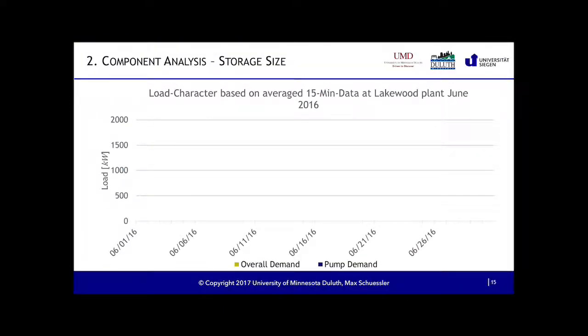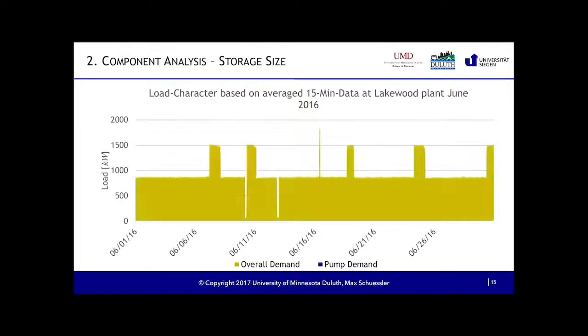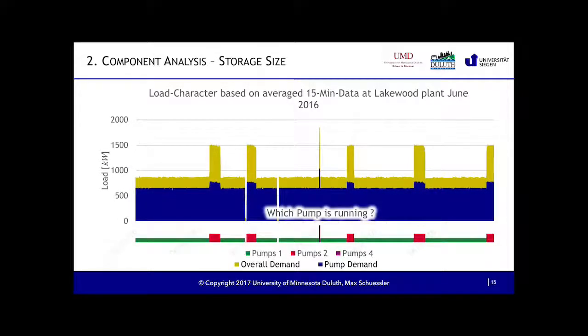And now I looked into the technologies. I know what something like this could look like, but what do I actually need at the Lakewood plant? And so the next thing is the load character of the Lakewood plant. And this is the data we get from our utility, from Minnesota Power, what the grid actually sees, what we consume down there. And what you can see is that we have 3 distinct levels our Lakewood plant operates on. We have the 900 kW line, we have a 1500 kW line, and we have a spike at 1800 kW roundabout. And as I mentioned earlier, the pumps and how they are set up align quite well with which pump is running at which time, which is pulled from the system that the city uses right now.